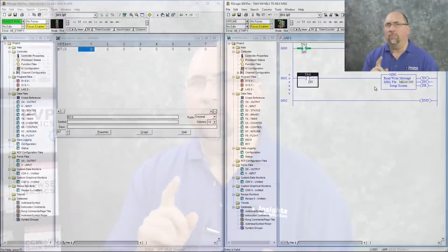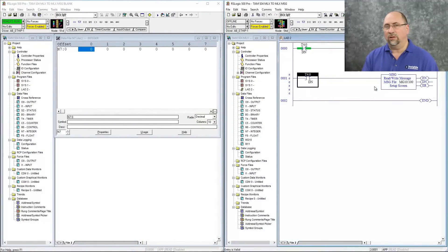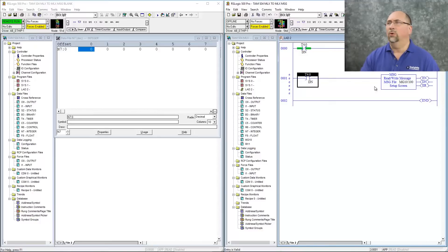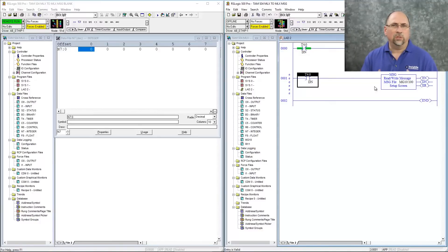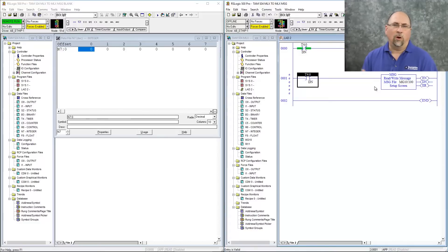So keep that in mind. Every Allen-Bradley PLC has a message buffer, and that buffer can only queue up so many messages before it gets full and starts throwing away new requests for messages until there's room in the buffer. Every controller has slightly different parameters, and every channel has slightly different parameters of how many messages it can store and queue before new messages start getting disregarded. So it's always a good idea to interlock your messages or to trigger them off of a timer.